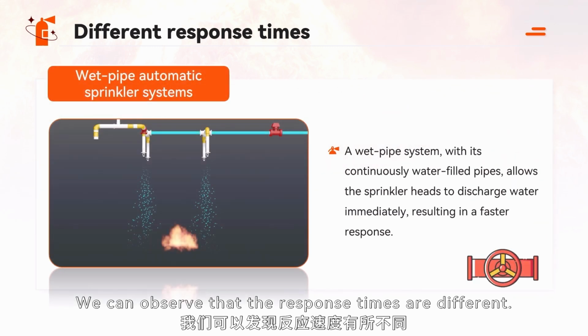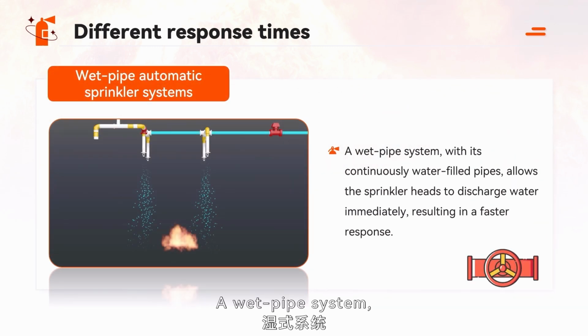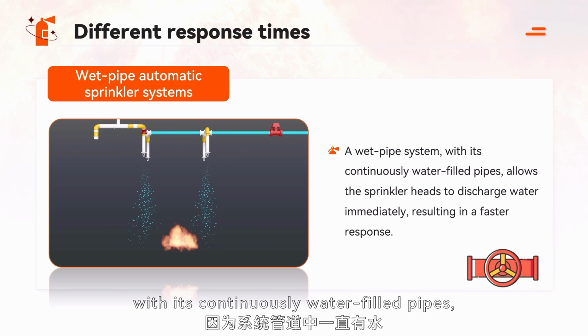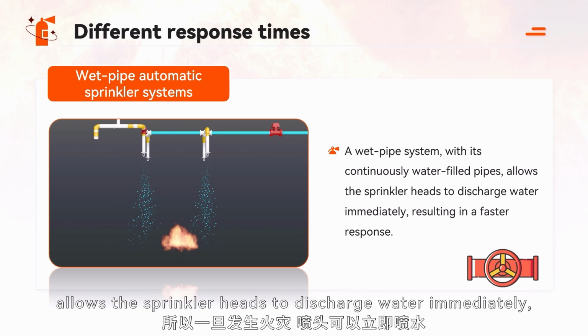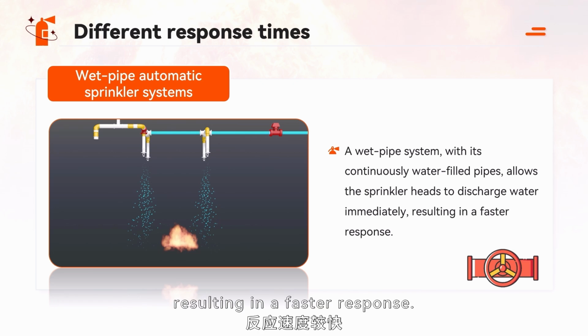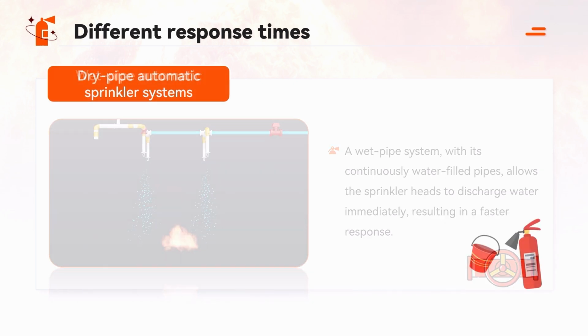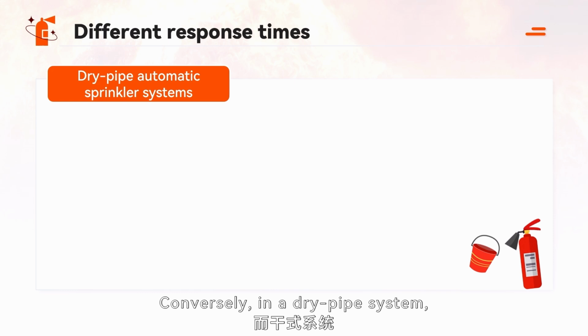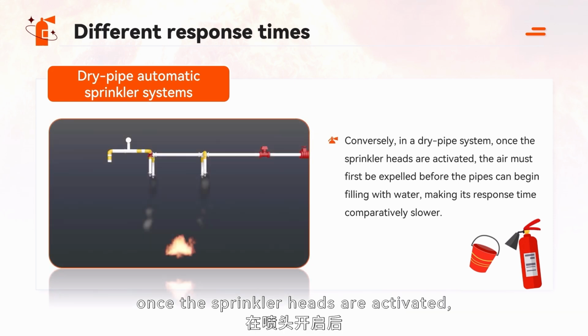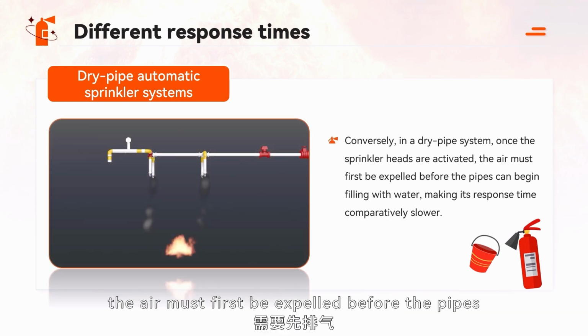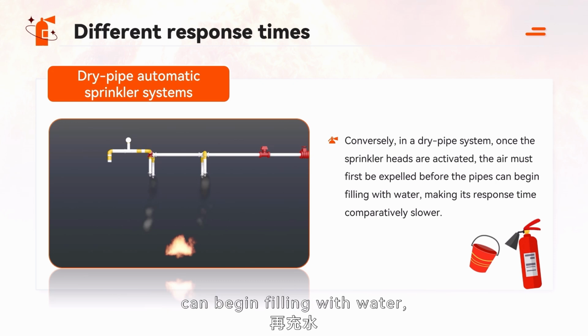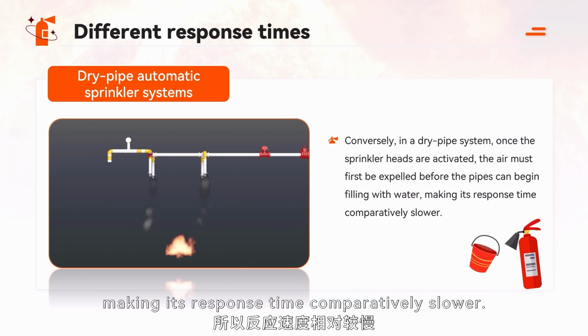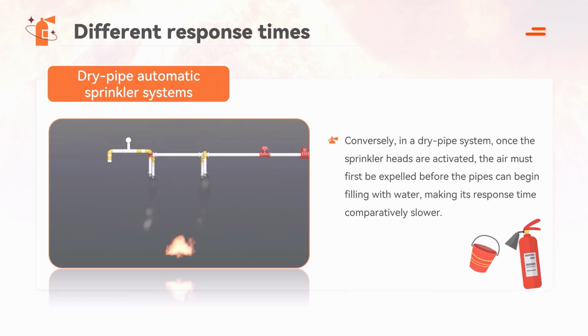We can observe that the response times are different. A wet pipe system, with its continuously water-filled pipes, allows the sprinkler heads to discharge water immediately, resulting in a faster response. Conversely, in a dry pipe system, once the sprinkler heads are activated, the air must first be expelled before the pipes can begin filling with water, making its response time comparatively slower.